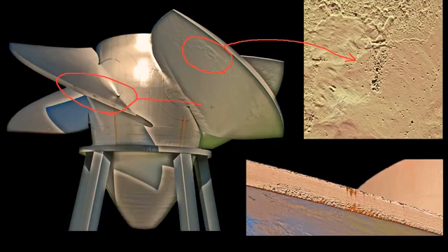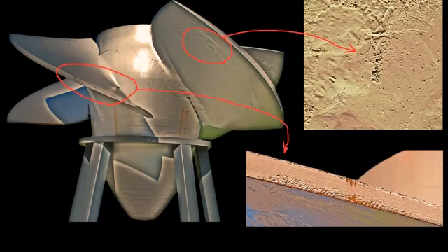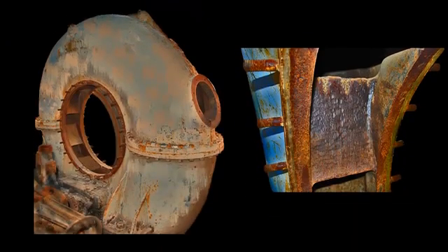Another example of cavitation is located in approximately this area of the blade tip of the turbine runner. This next example is also of a hydroelectric facility. This particular facility dates back to the early 1900s and is now abandoned. This is a picture of a horizontal turbine housing.